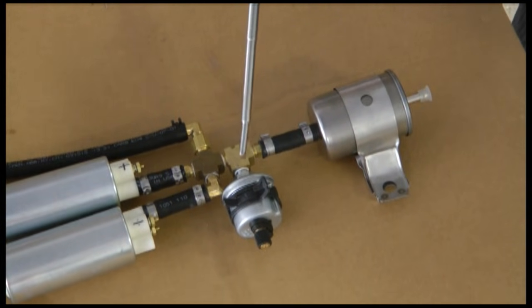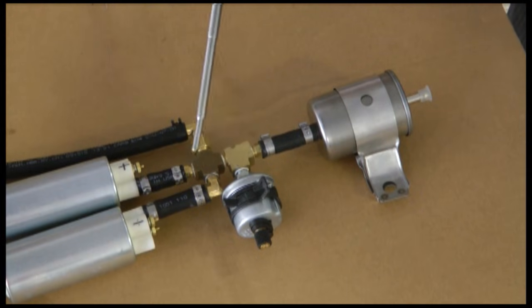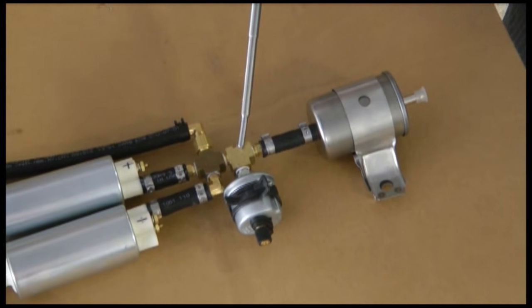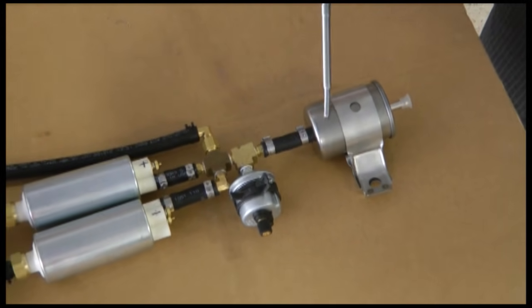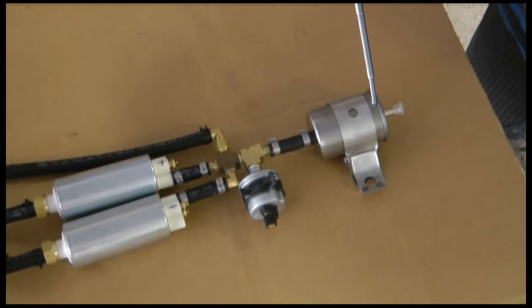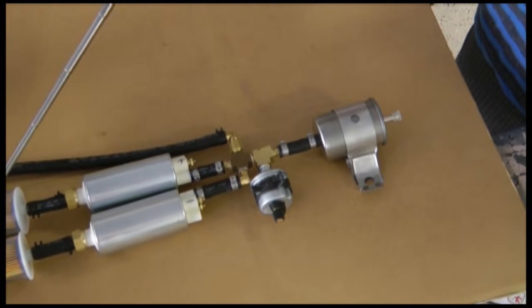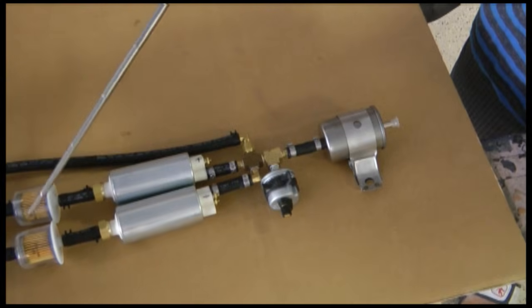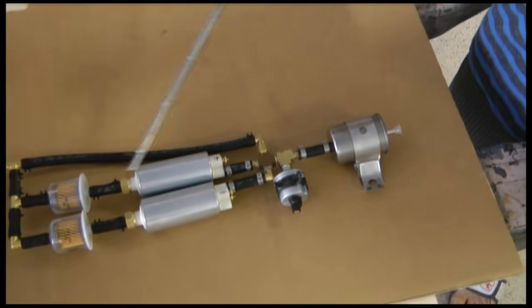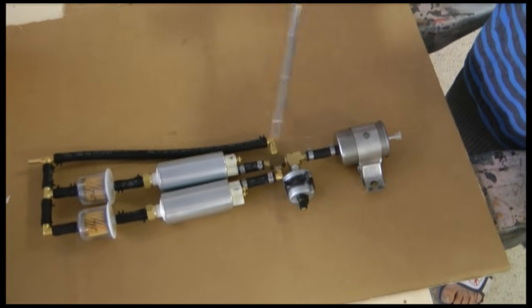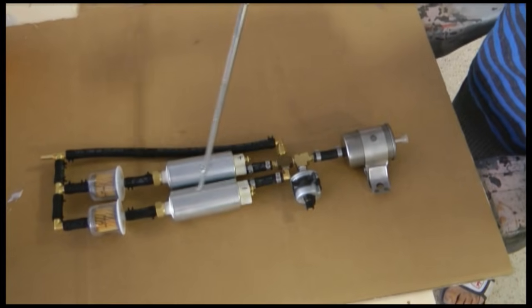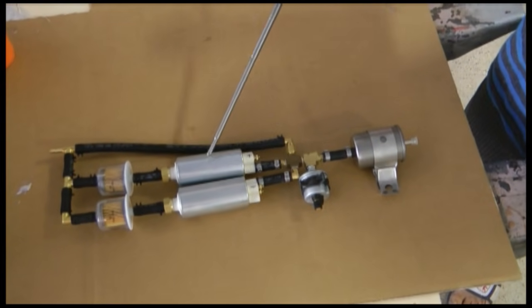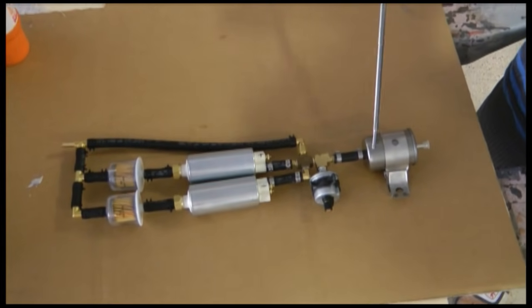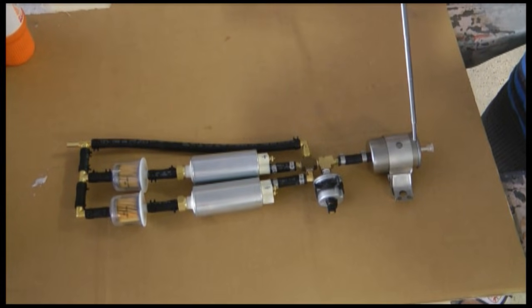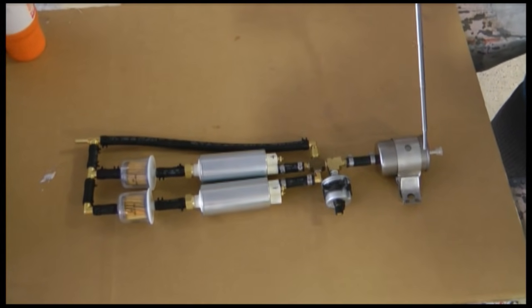For us, it was convenient to put it right here because we were able to put it in a threaded fitting, and we're not so concerned about this filter clogging because we have primary filters, and the only possible contamination that can get into this filter would be a deterioration of the pumps themselves, which is extremely unlikely, and even if they did, there would be very little contamination in the filter prior to changing it on the annual inspection.